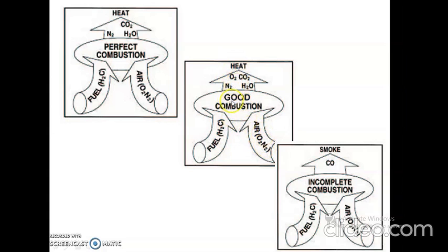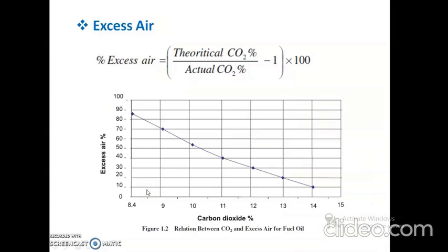That is good combustion. And incomplete combustion is, of course, as I told you, CO in the exhaust gas, which is nothing but the indication of incomplete combustion. So in order to monitor the performance of the boiler, always monitor the exhaust gas composition in order to understand the combustion inside the furnace.